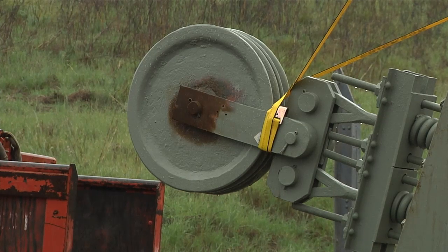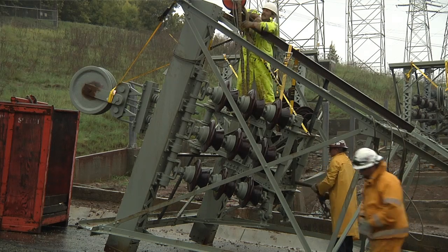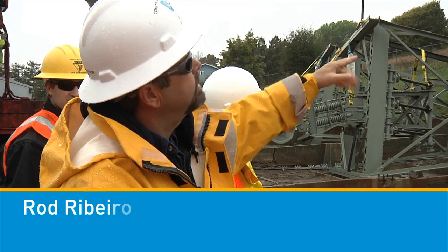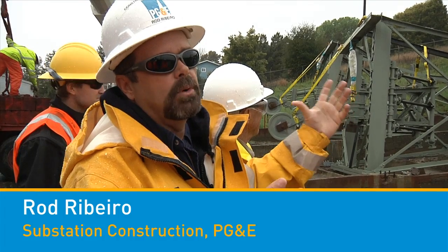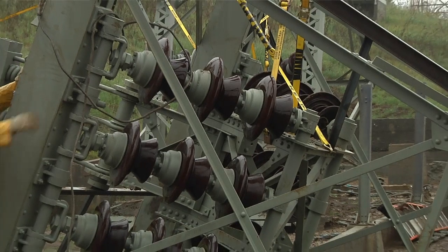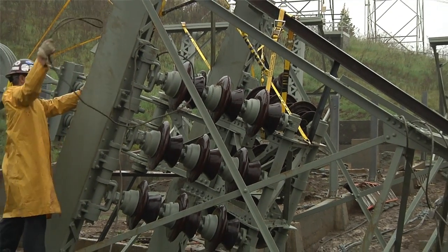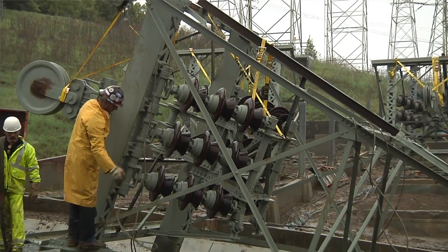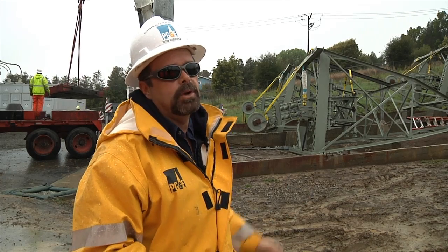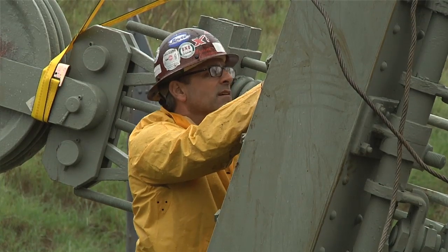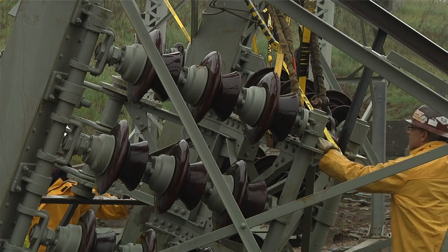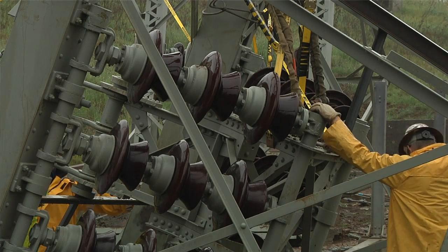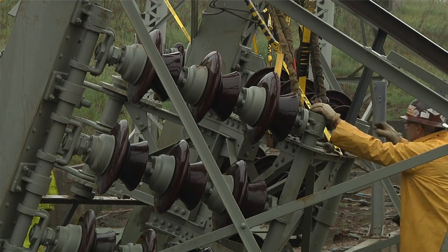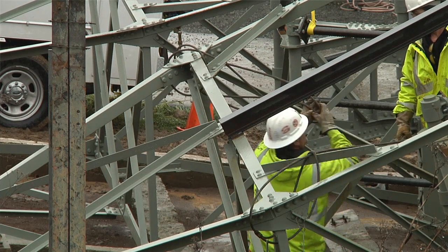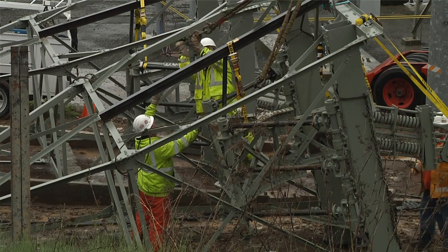The way they're designed, if you look at the center traveler in the middle of the structure, it's suspended on all sides, both sides and on the bottom, with insulating glass. The glass itself is about 80 years old, so the integrity of the glass was suspect, and we were concerned about it falling apart as we tried to move it. And in fact, it has. As we've taken these apart, the glass is failing. So what we did is we suspended the weight on top and bottom so we could get the glass out.